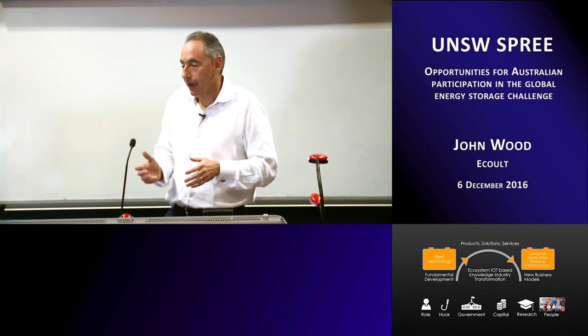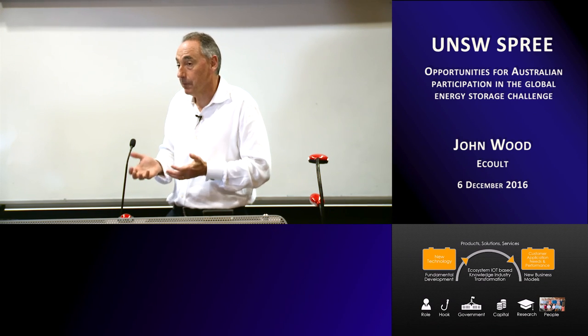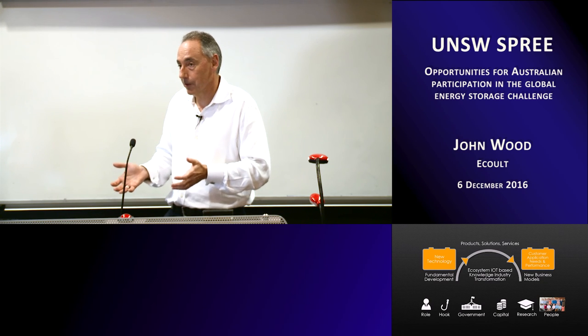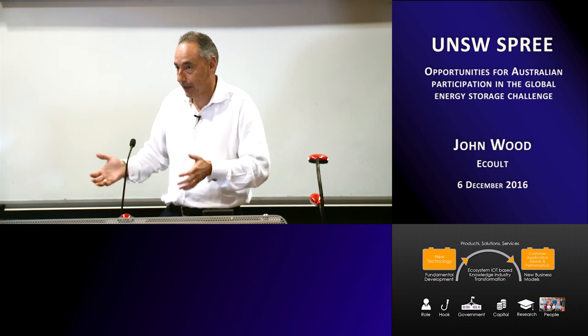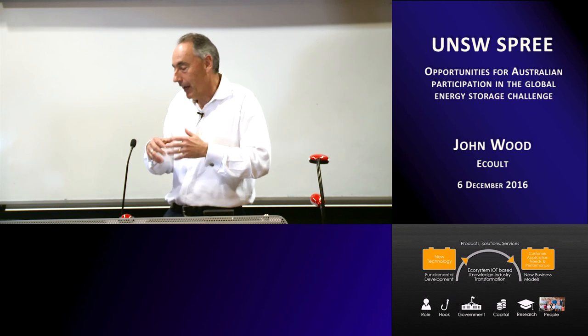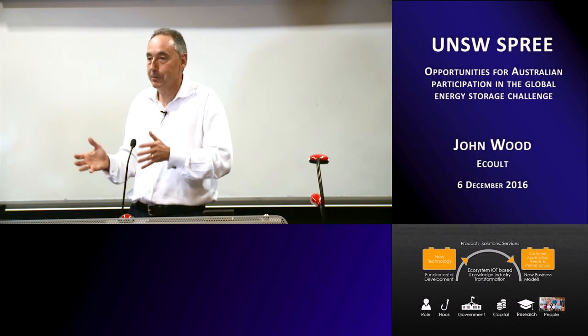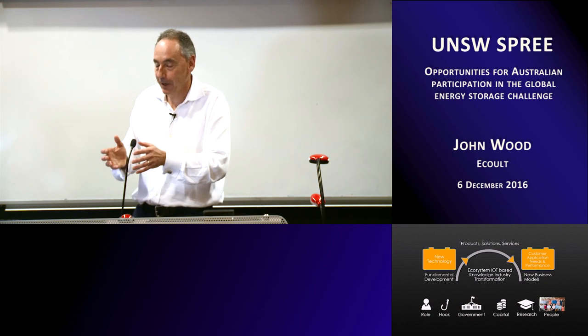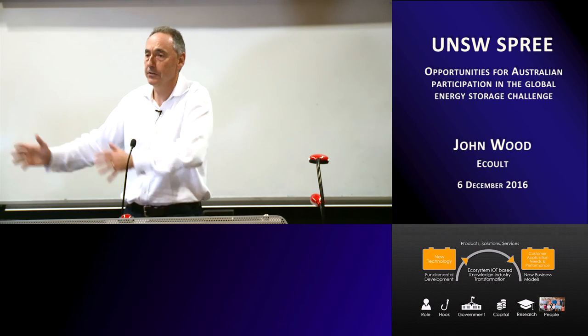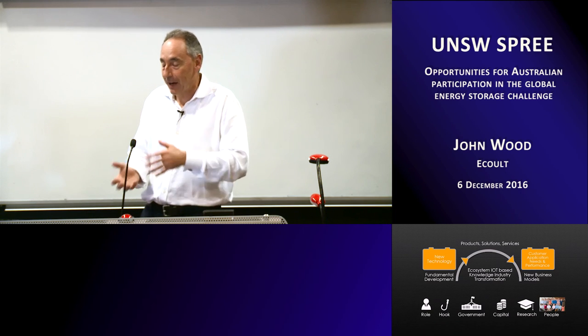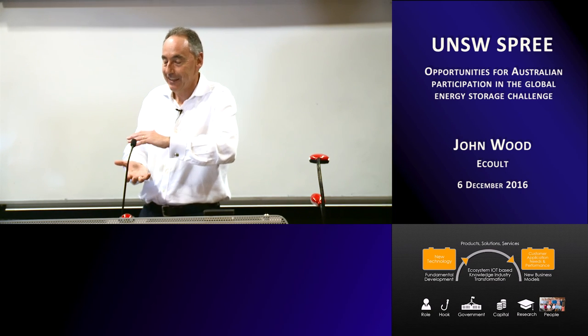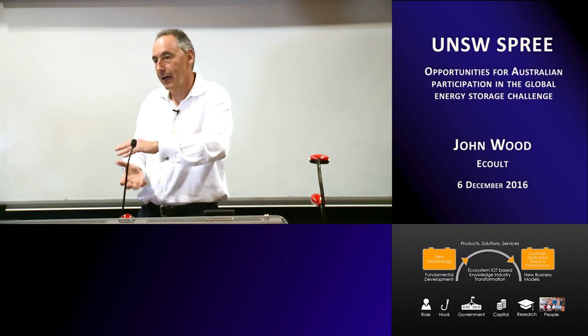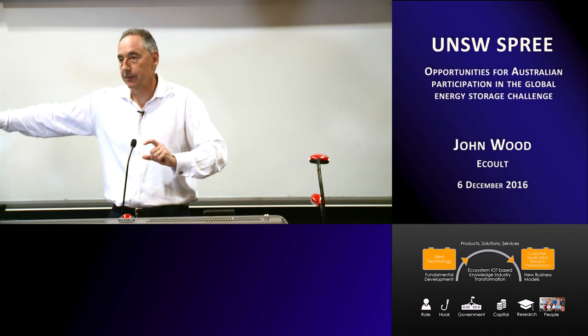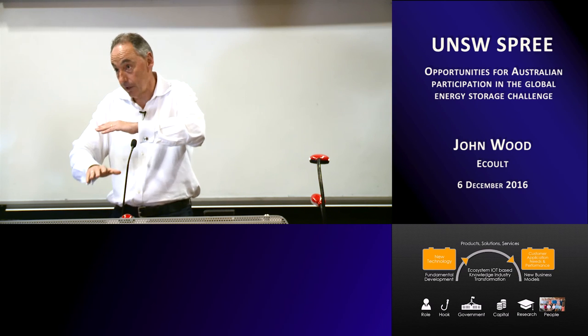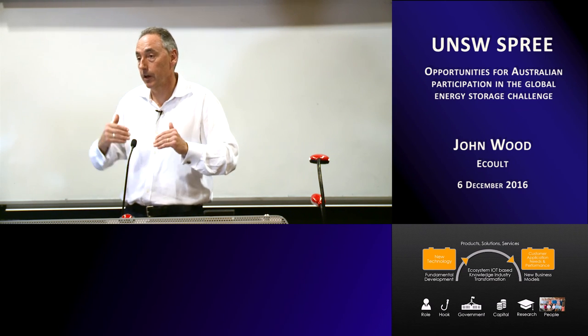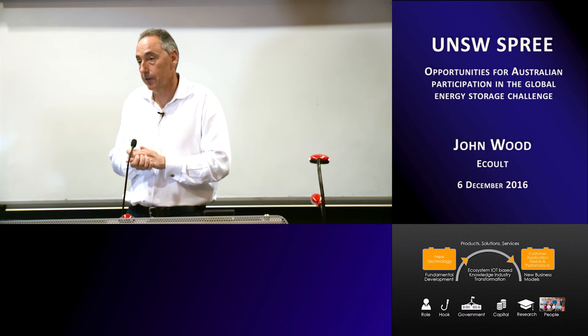I'll caveat it by saying we haven't had UltraBatteries in the field for 10 years yet, so I'll caveat everything by saying that, and everything is not as straightforward as a spreadsheet — there are peculiarities about the way the grids corrode that are important. But in general, if you're running lead acid technology in a partial state of charge, those secondary life factors are pushed way back. They're much lower than if you're running the battery on float, or in the top 20% of the battery.